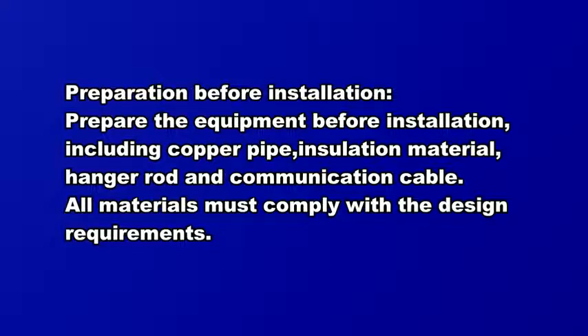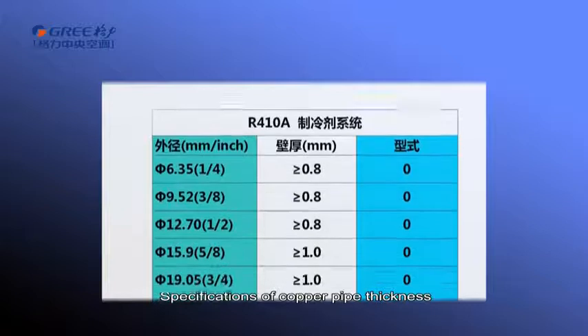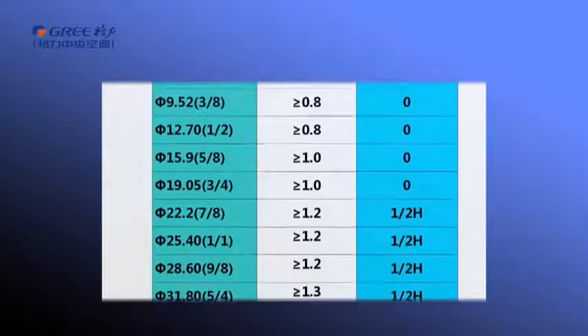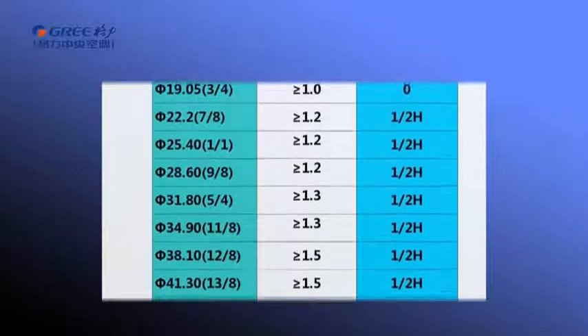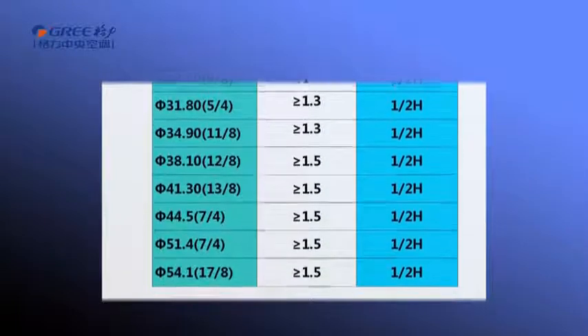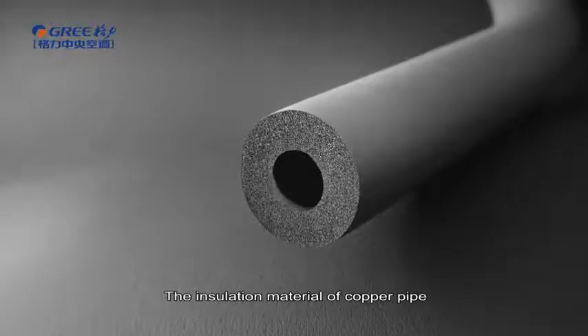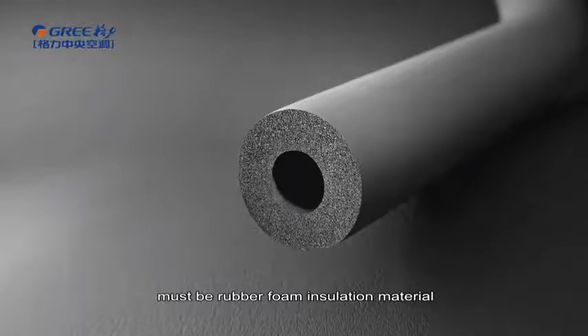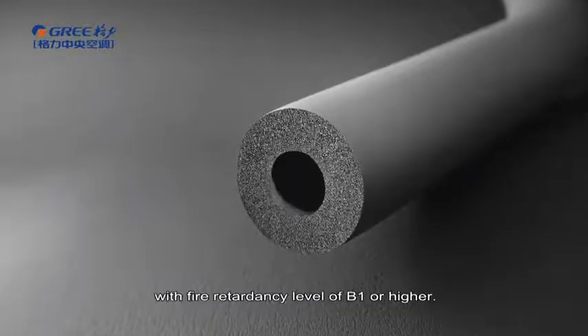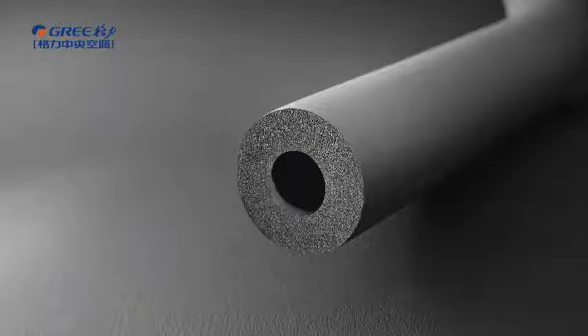Preparation before installation. Prepare the equipment before installation, including copper pipe, insulation material, hanger rod, and communication cable. All materials must comply with the design requirements. Specification of copper pipe thickness. The insulation material of copper pipe must be rubber foam insulation material with fire retardancy level of B1 or higher.